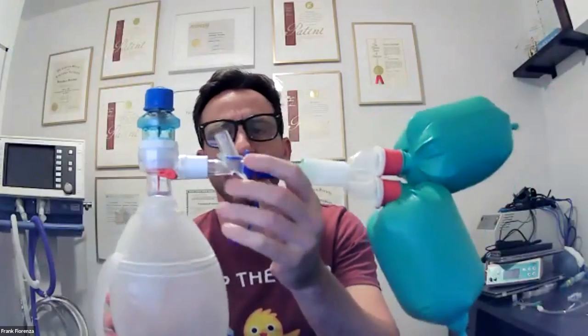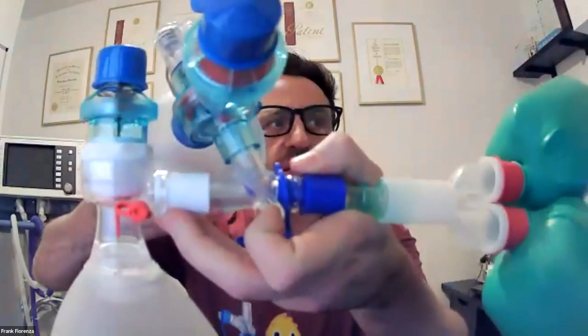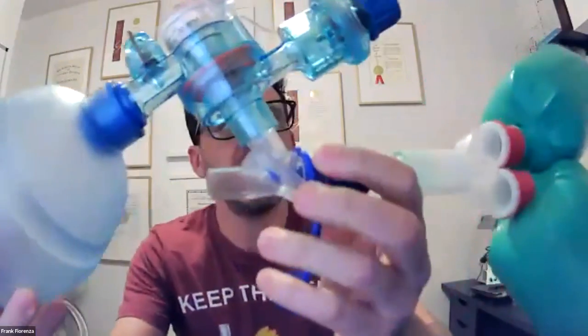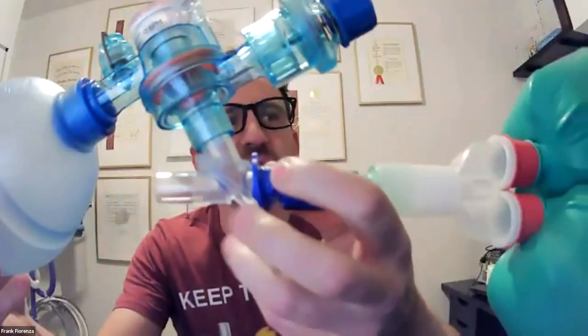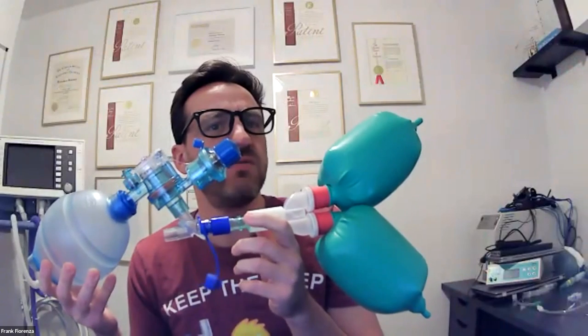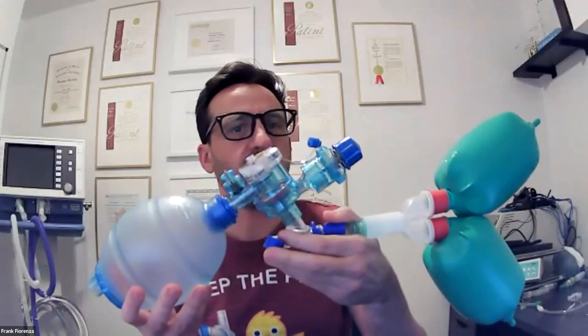So now in this scenario, they say, Frank, go off and go to MRI. So I uncap, I connect my secondary ventilator source, hook it up, turn it on. If you saw that flip, it flipped. Now you can see the valve is closed off to the ventilator port. Nothing happened to the lungs. I know it's very boring, but they didn't collapse, they didn't reinflate. And I would cap that port and go off about my merry way.